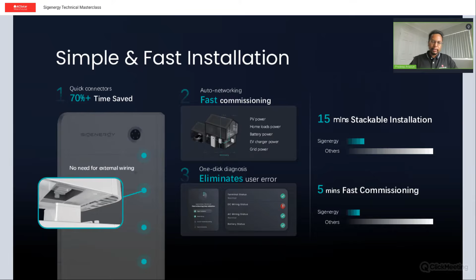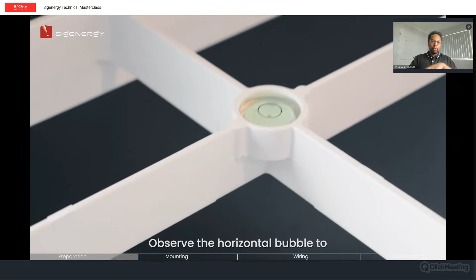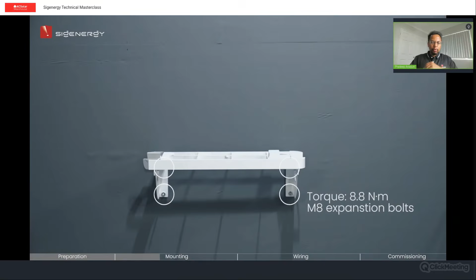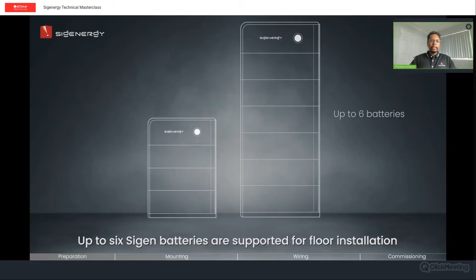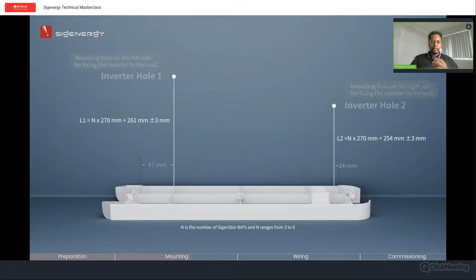You can do floor standing or wall mounting. On the floor, you can put up to 6 batteries under the inverter. On the wall, you can put up to 2 batteries. The bracket is the same, so the wall mount bracket can also be used for the floor mount, it just comes with a couple of extra brackets. So up to 6 batteries, and if there's an EV DC charger, that takes up 1 slot, so you can have 5 batteries plus an EV DC charger.